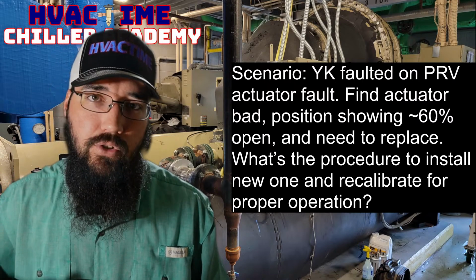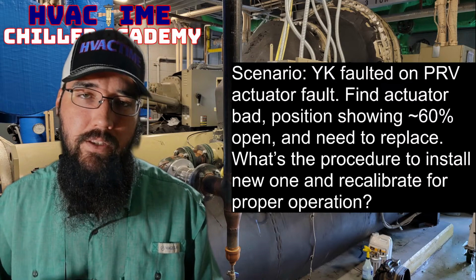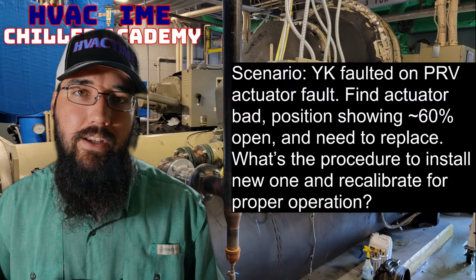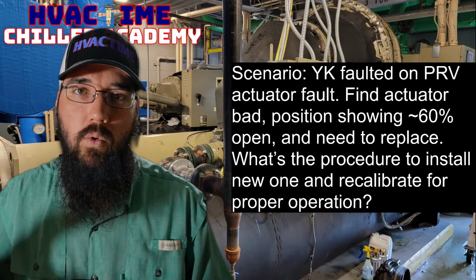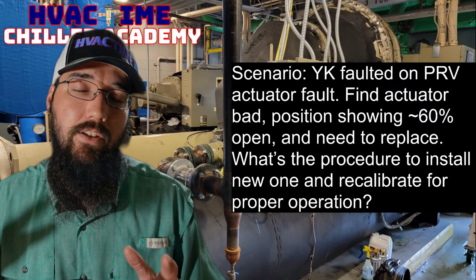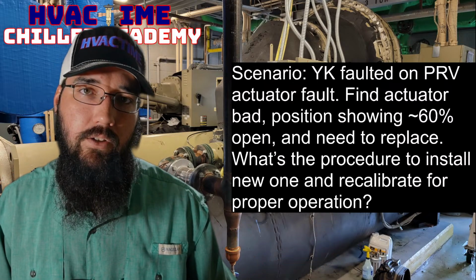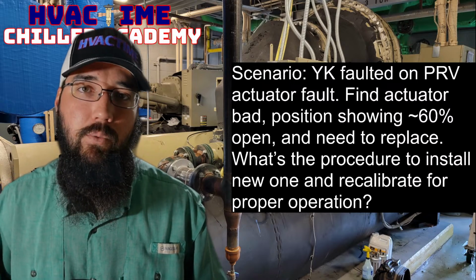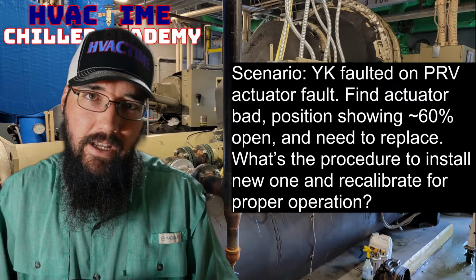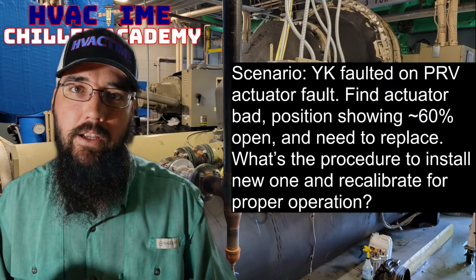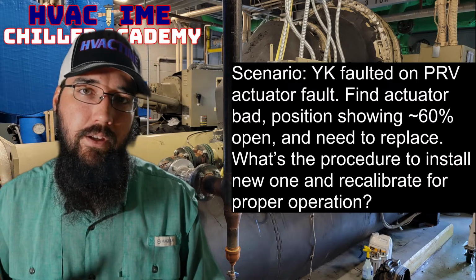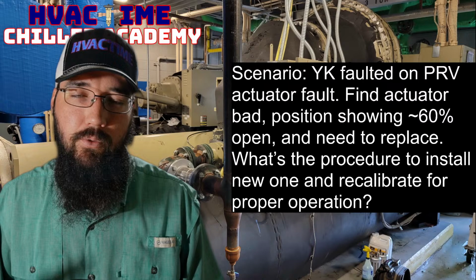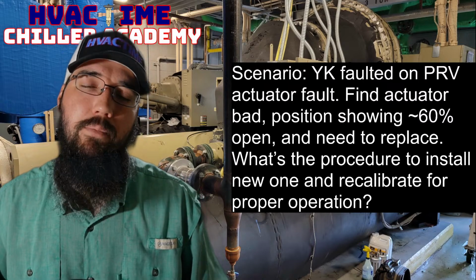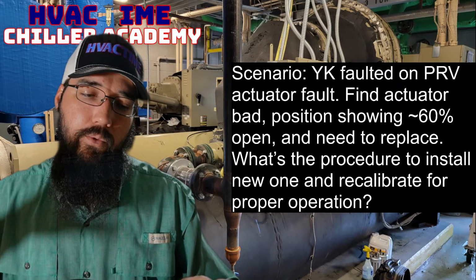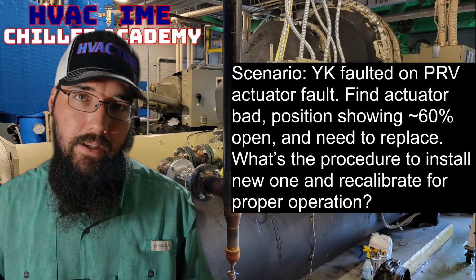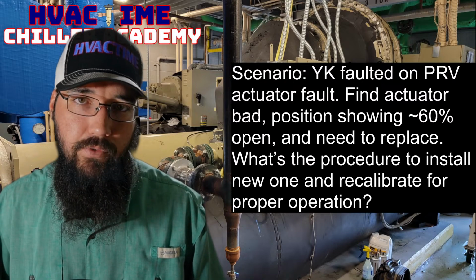Make sure that as you're swinging, it's very important that the linkage in between doesn't get into any kind of bind, so it's not going to have issues getting hung up. Just watch it. It should be a nice, gradual, easy, smooth flow from 0% to 100%. If you see it hiccup or glitch at any point, note that you can manually open or close it 100% from the panel with the machine. I'd do all this with it off, don't do it running, but you can do a manual operation on that PRV. Just watch it and make sure it's not binding up at any point, because that will only cause further failures down the road.